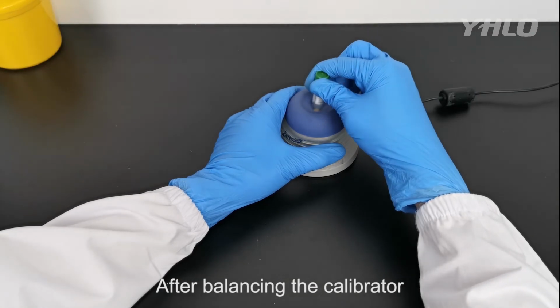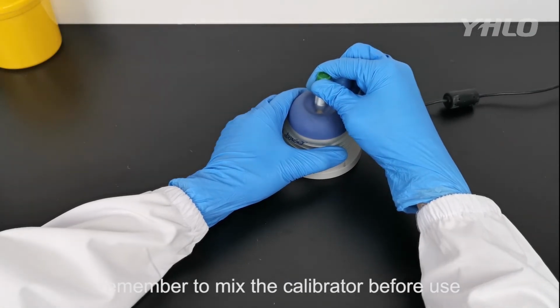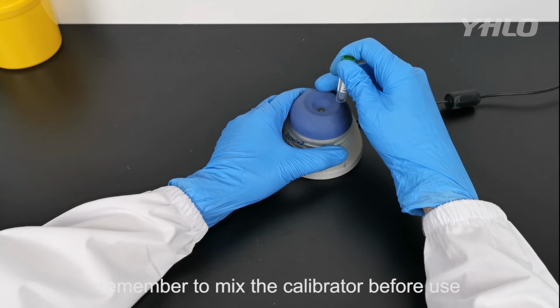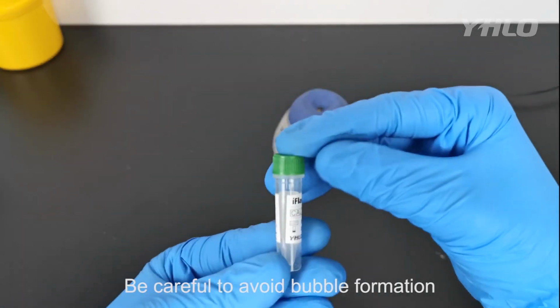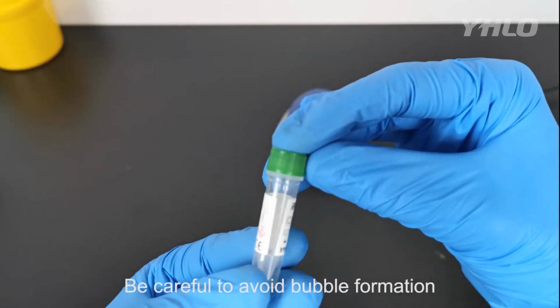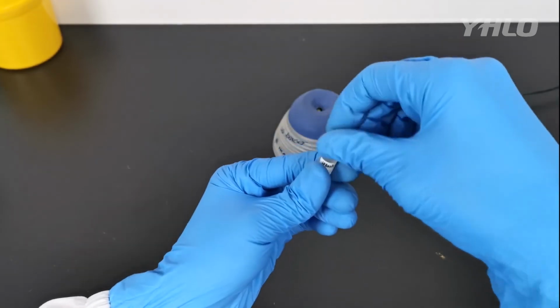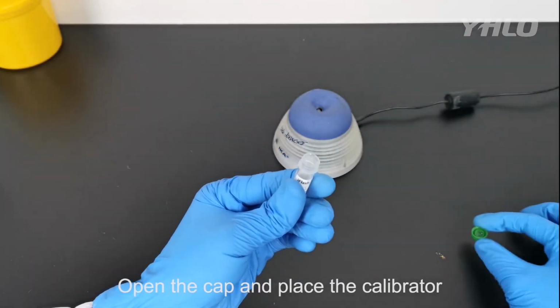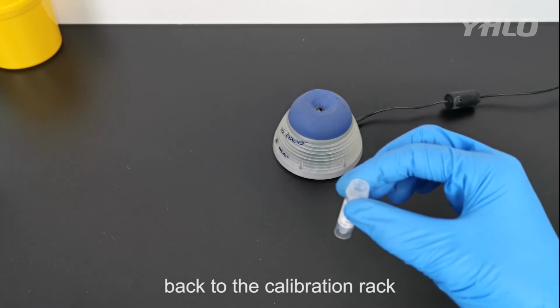After balancing the calibrator, remember to mix the calibrator before use. Be careful to avoid bubble formation. Open the cap and place the calibrator back to the calibration rack.